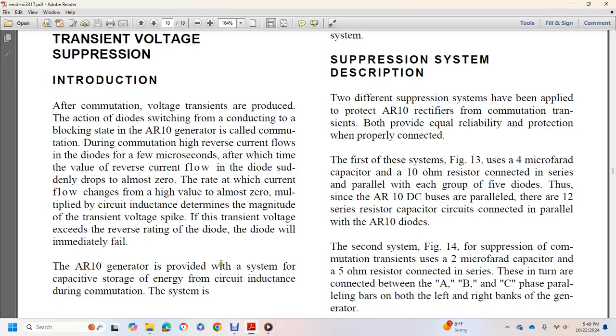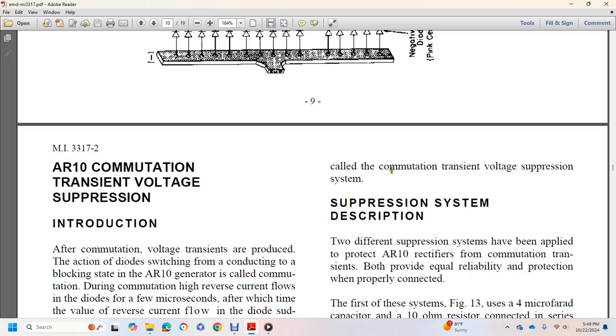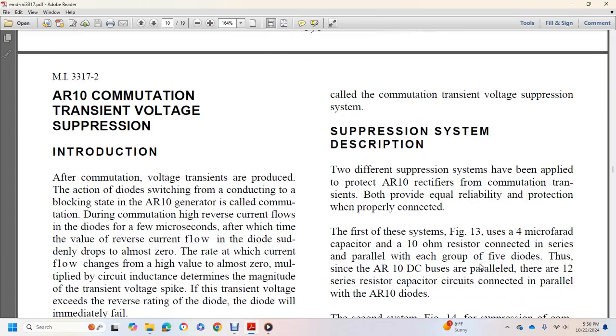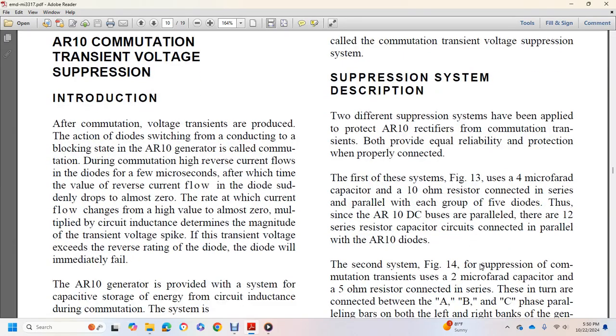With the AR10 generator provided with the system for the capacity for the storage of the energy for the circuit inductance during the commutation, the system is called the commutation transient voltage suppression system. Two different suppression systems have been applied to protect the AR10 rectifier commutation transient, and they provide equally reliable protection, properly connected.